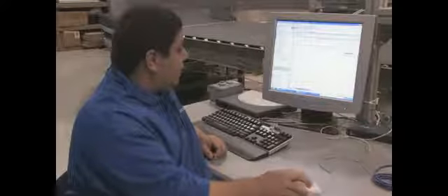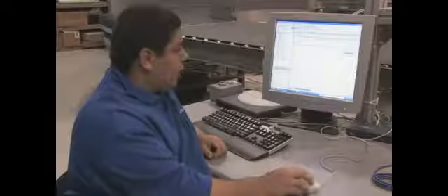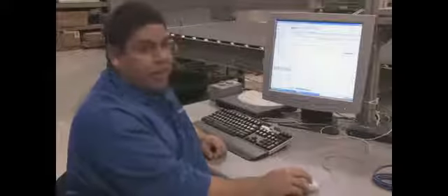This is the sample program that we supply for our customers who are trying to work with the scanner on a PLC. The trigger bit for our scanners is output word 0, bit 7. This is the trigger bit in the scanner that needs to be set if you're going to use this particular feature. The next rung shows that whatever data we read will be in the input register, and we're going to copy that and put it in a raw string.